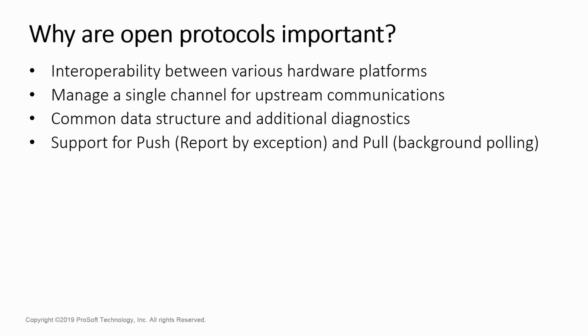So why are open protocols important? The interoperability between various hardware platforms is a huge customer benefit. A customer could have 10 different hardware types as part of their system, but they could all talk one common language, either for communication between them or back to the top end. That ensures they don't need 10 different top ends to manage the entire thing. The common data structure in some of these open protocols also allows a lot of diagnostic information to come through, rather than just status or value information, which was what Modbus did.